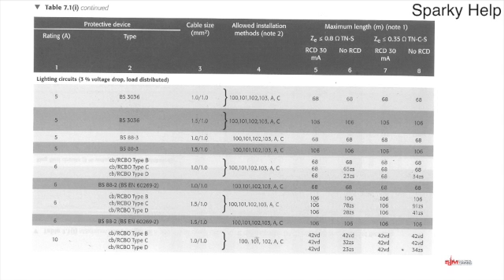This is a particular page, and there are many pages like this that cover most standard types of circuits. If we look at this, we have got multiple columns, and in the first column, for lighting circuits, it gives you typical circuit breaker sizes. So in a domestic installation you would probably put a 6 amp, and we would probably go for a type B. Then the third column over gives you conductor sizes. So are we putting in a 1 mil, or a 1.5, or whatever it happens to be. So let's go for 6 amp type B and a 1.5 with a 1 mil earth, and we can see that on there. And if we look across, the fourth column over gives us installation methods.